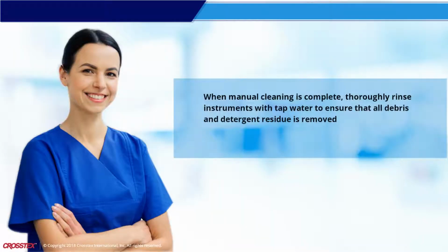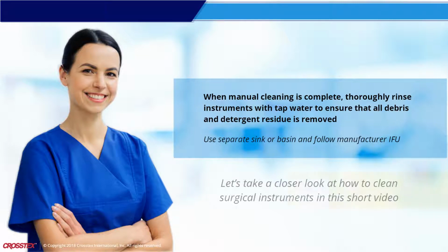When manual cleaning is complete, thoroughly rinse instruments with tap water to ensure that all debris and detergent residue is removed. Rinsing should be performed in a separate clean sink or basin. It is important to follow cleaning detergent manufacturers' IFU regarding the number of rinses to be performed.